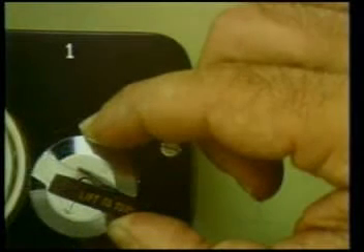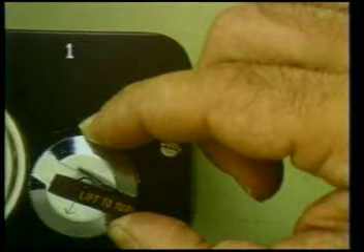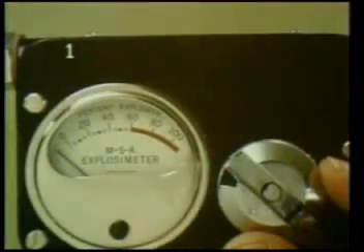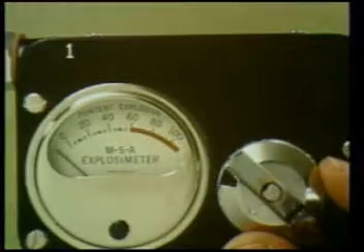So much for theory. Now let's go through the sampling routine with the explosimeter indicator. There are 7 easy steps. 1. Lift the on-off locking bar of the rheostat knob and turn it a quarter turn to the right. This closes the battery circuit, so the needle may either move rapidly upscale and then return to a point below 0, or drop directly below 0.